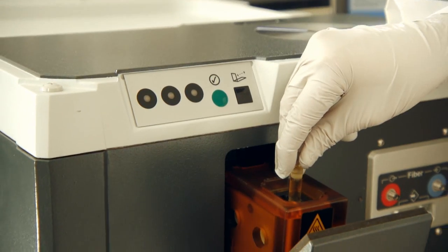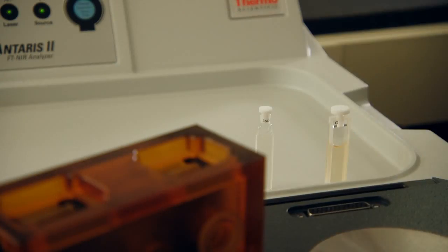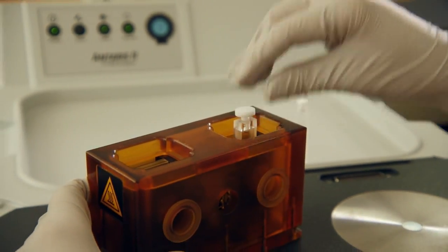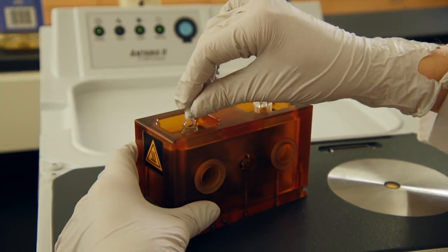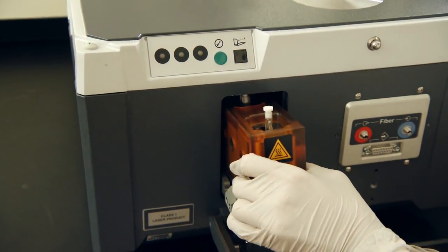For the analysis of liquids, the Antaris features a temperature-controlled transmission module that automatically analyzes two samples, while a third dedicated reference position collects the background spectrum, ensuring your operators produce accurate results independent of sample placement.